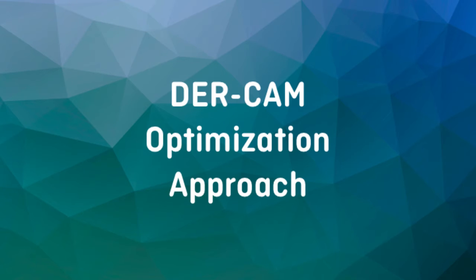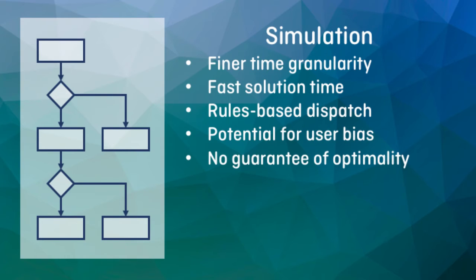One key thing to note: there are, of course, other software tools that assist with microgrid design. Several of these tools use a simulation approach to find a solution, rather than the optimization approach used by DerCam. Simulation can be very useful, as it often allows for a more detailed examination of operating conditions, for instance by modeling all 8,760 hours in a year. For dispatch of DER technologies, however, simulation typically relies on rules-based strategies. When certain conditions are met, different DERs might be dispatched to respond in a scripted manner. Rules-based control strategies can vary in complexity, but in practice they are often influenced by the past experience or preconceptions of the modeler. As a result, the simulation approach does not guarantee an optimal solution.